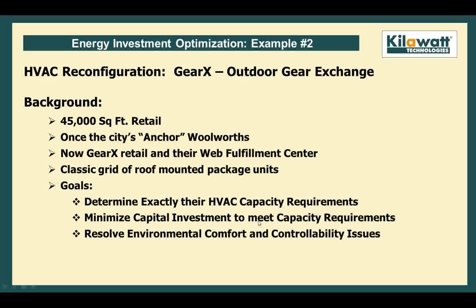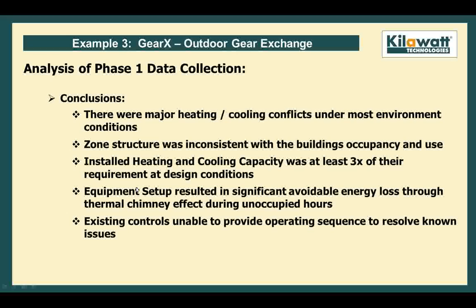In this case, we collected electrical consumption data on the HVAC system to figure out what the realized operating sequences were, collect the data from each of the 6 zones to find the pattern of how they were operating together. The conclusions were very simple. They were not operating together. The 6 zones were operating completely independently with a few programmable and 2 mechanical set thermostats. These 6 zones were fighting more than Congress is. The result is that the zones were completely inconsistent with the uses. They had more than 3 times the capacity needed to condition their space, and we also identified something very interesting, and that was a thermal chimney effect during unoccupied hours. I'll go into more details on that in just a second.